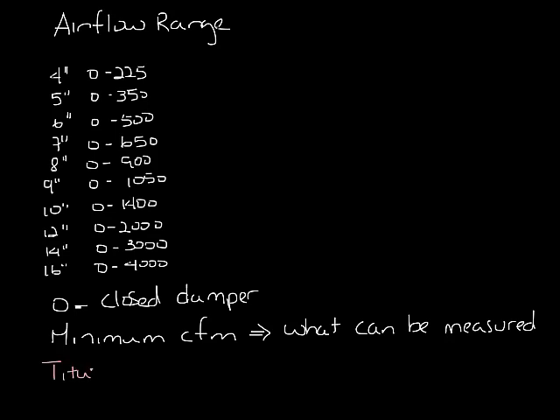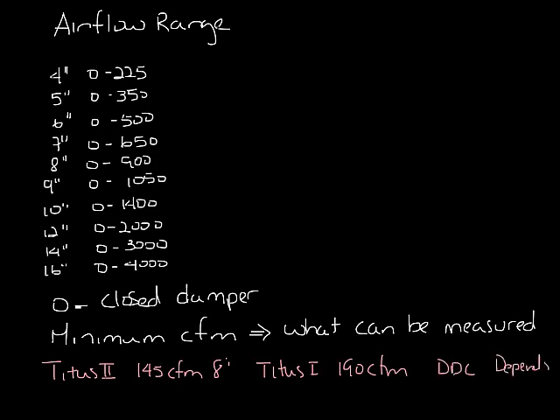For instance, our Titus II pneumatic controller can control down to 145 CFM on an 8-inch inlet, but the Titus I only goes down to 190 CFM. And then someone else's DDC controller could even go lower than that maybe. So it's really dependent on what the controller can handle. I know a lot of people don't use pneumatics, but I chose pneumatic controllers because we know exactly what these can control down to.